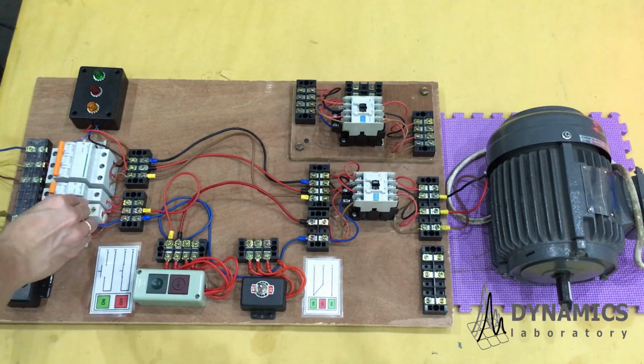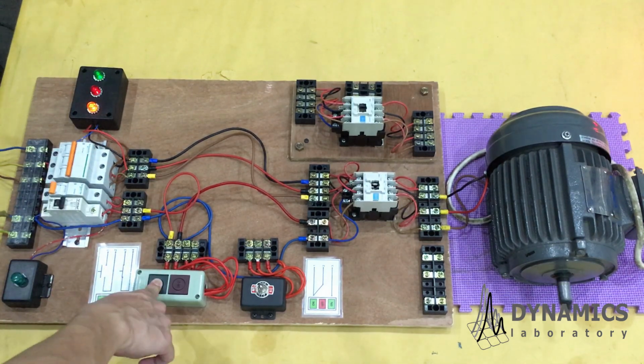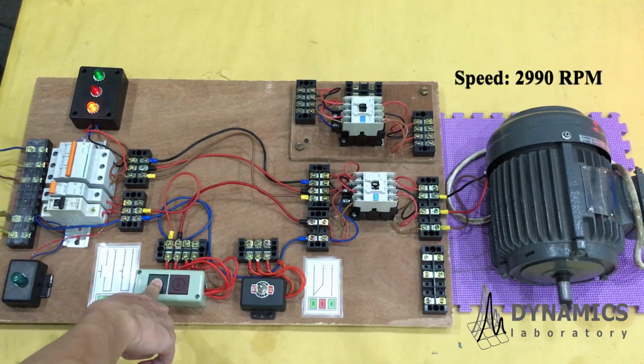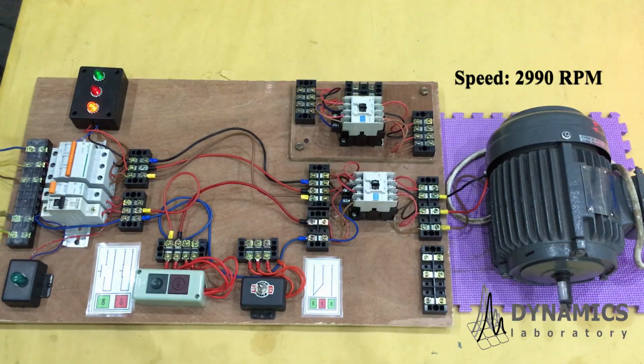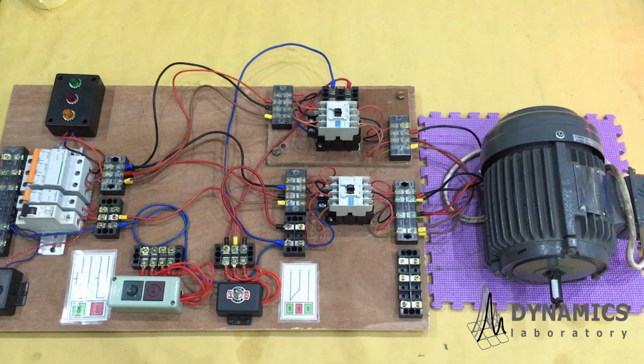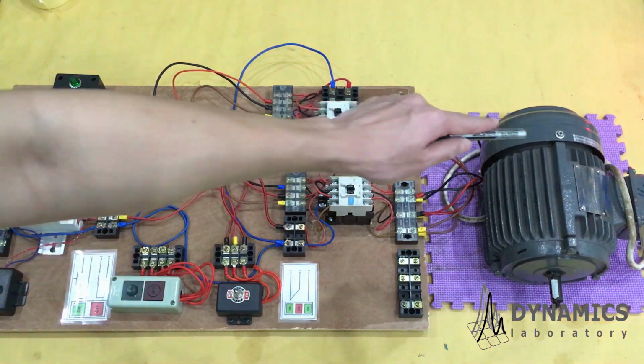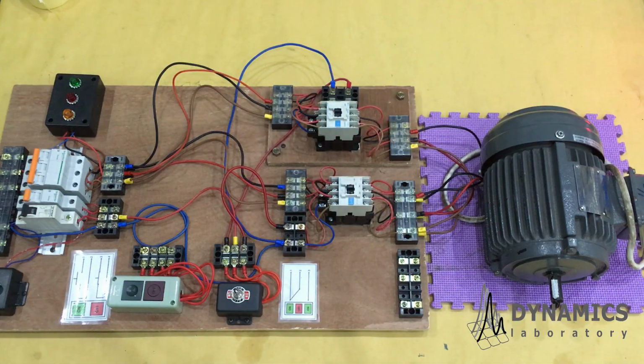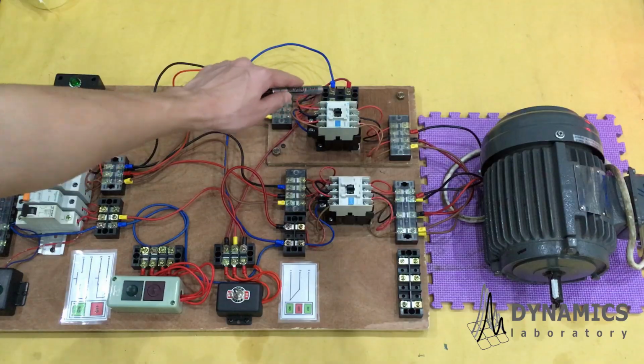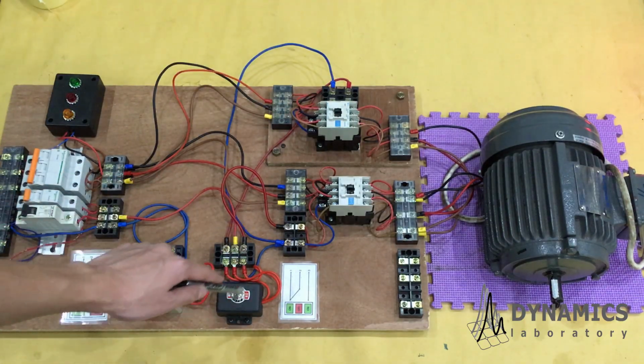Let's try. When I push the on button, the three-phase AC motor is running. And I release, the three-phase AC motor is stopped. That's how we operate three-phase AC motor. Last load circuit. In this circuit, we want to reverse the rotational direction of three-phase AC induction motor. Therefore, we will utilize two contactors and also switch control circuit.